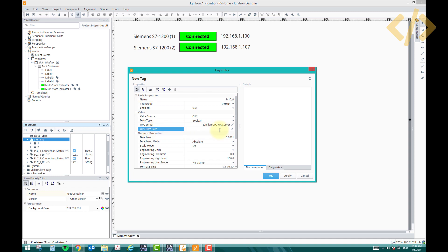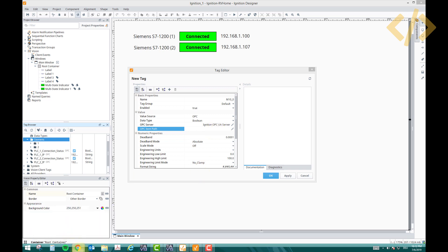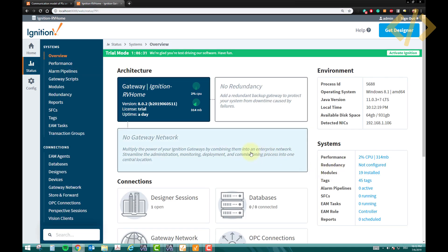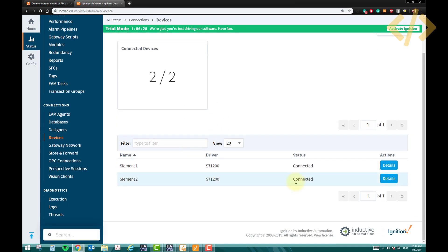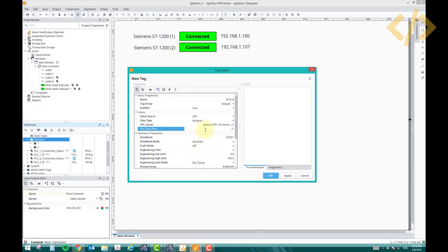In the OPC item path, this is very important: you have to write the name of the PLC in brackets. Go back to Ignition, go to Status, then go to your Device and check the PLC name — it's 'Siemens1'. So in the item path, write [Siemens1] first. Then instead of M10.0, you must write MX10.0 — the X defines it as a boolean address. Then click Apply and OK.